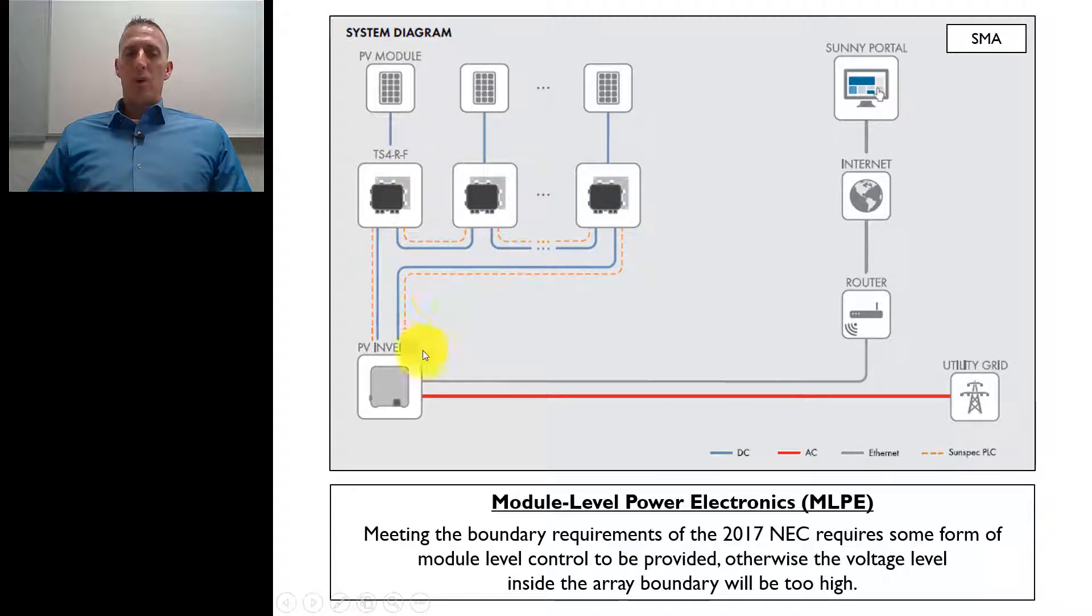And when rapid shutdown is initiated, it's going to basically break down this array and reduce those voltages to specific levels that within the array boundary would be less than or equal to 80 volts. And then outside the array boundary, this is where we would be at 30 volts or less within 30 seconds.